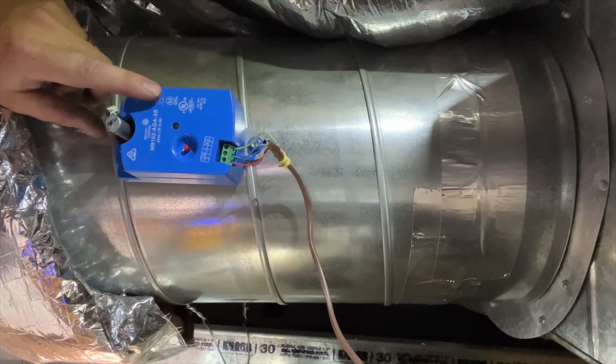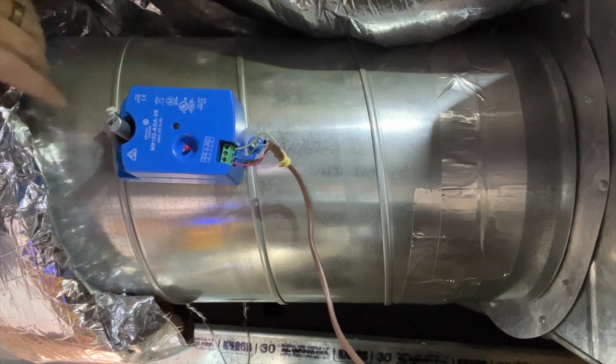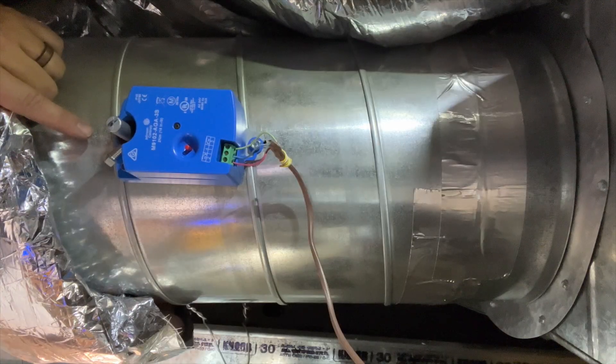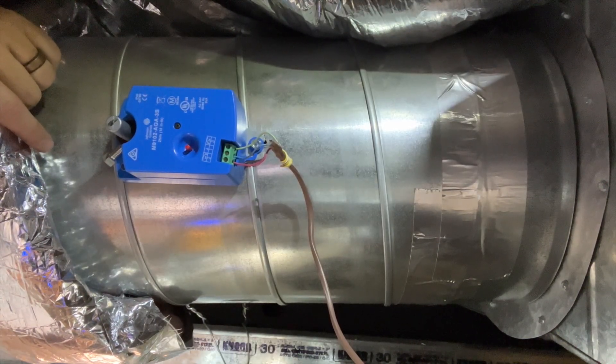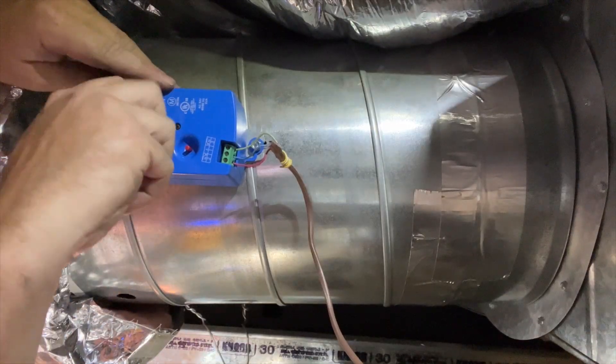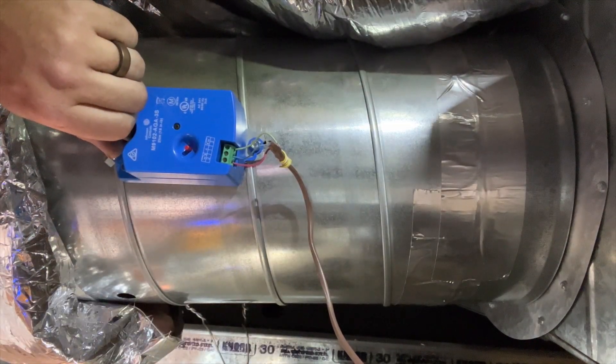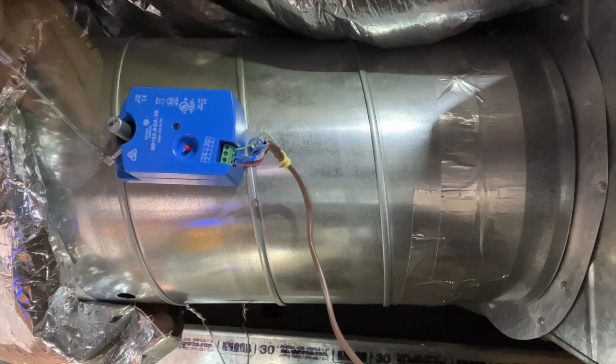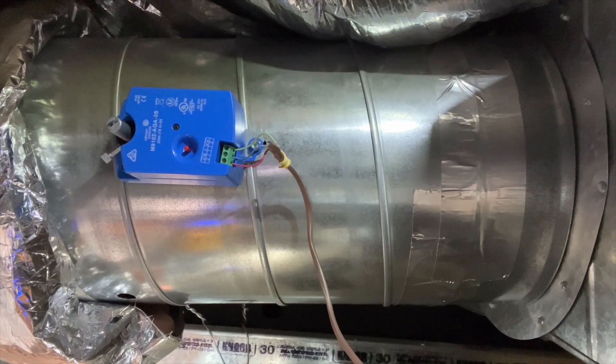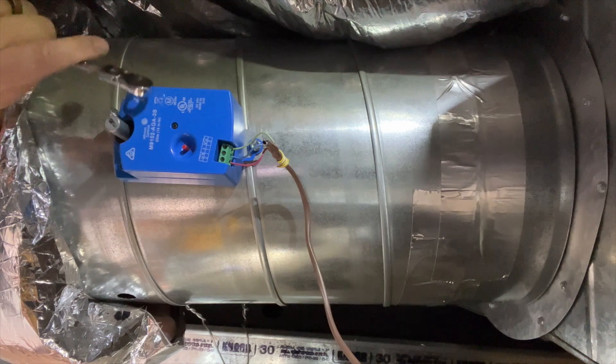I need to make sure that both zones are open, the actual dampers, because they're still loose. I'm aligning this damper actuator with the actual damper inside. This isn't attached right now, so right now it's currently going to be in the closed position. Now I'm going to go ahead and place it into the open position and you will see it is opening. So that is in the open position now. I need to make sure that my actual damper is in the open position. That is open. So now that we have verified that it's in the open position, we will go ahead and crank this down. Now we're going to close the damper, make sure that it works properly. It is now in the closed position, so this one is aligned.